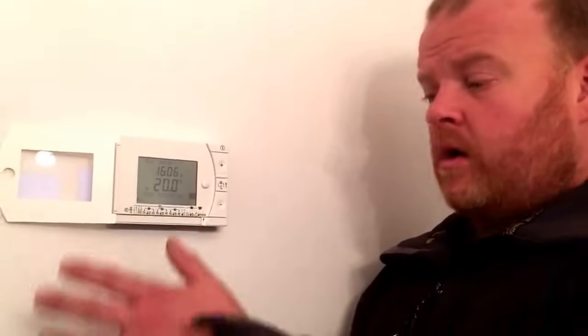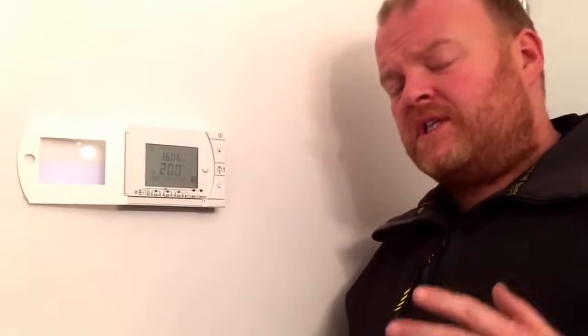Down to frost protection. Quite a handy little thing on this time clock. It's got frost protection. If you click it and leave it on that frost protection, it's going to ignore all your time settings, your temperatures you're wanting to achieve, but it's basically going to give you that backup of a frost start where it's going to bring your heating on if your temperature internally drops below 5 degrees. So if you're going away a period where there's a chance there could be a cold snap, some really bad frost, snow and such, if you stick it in frost protection, it'll basically protect you and hopefully you won't have any incidences of frostbursts in your house. The heating's going to come on and protect you.